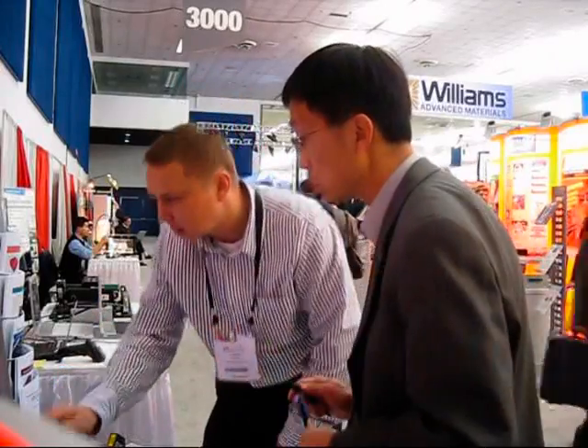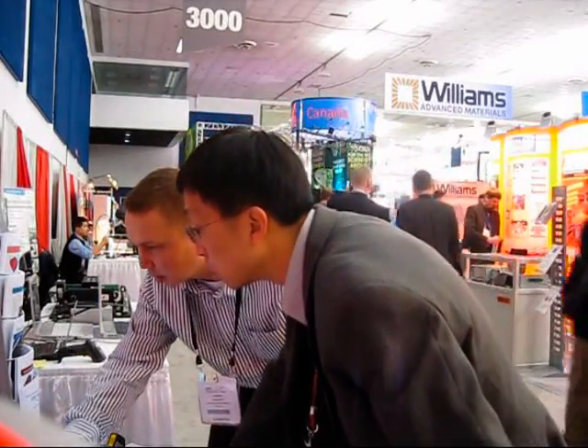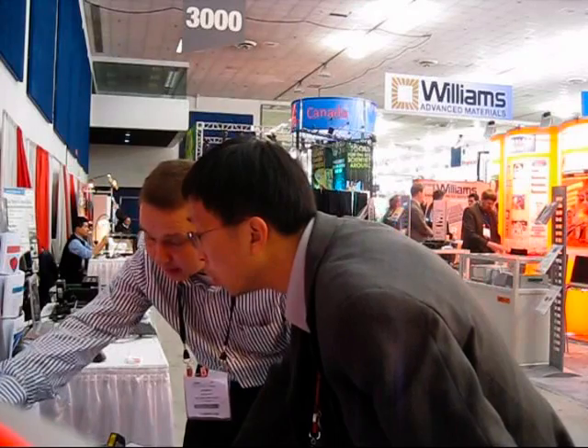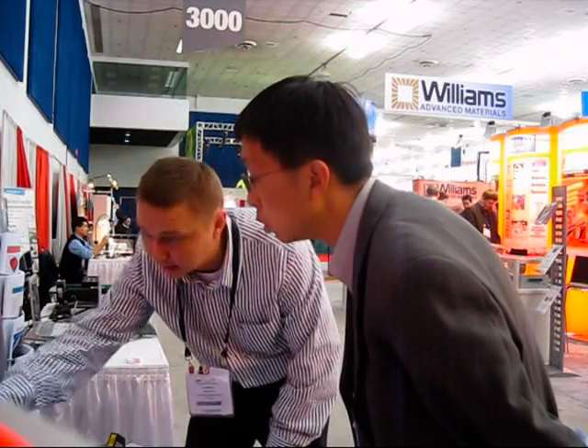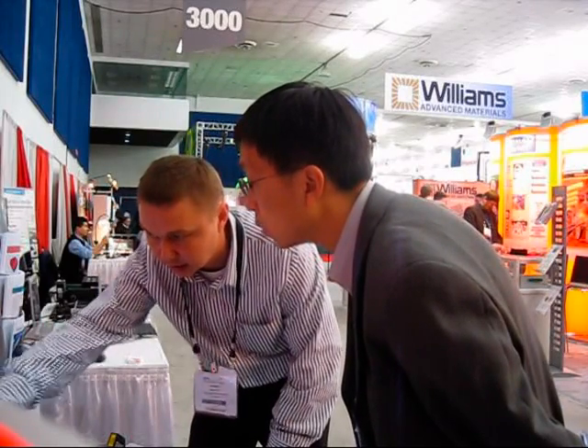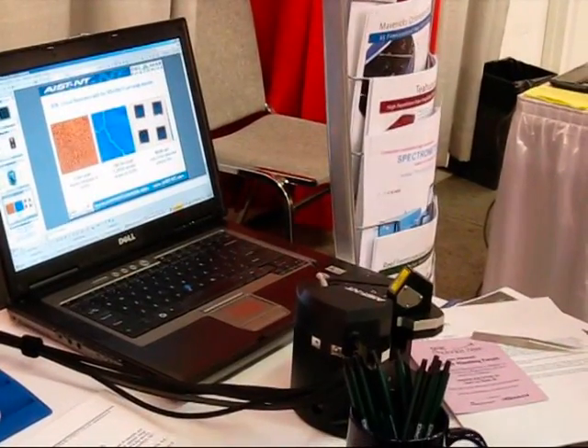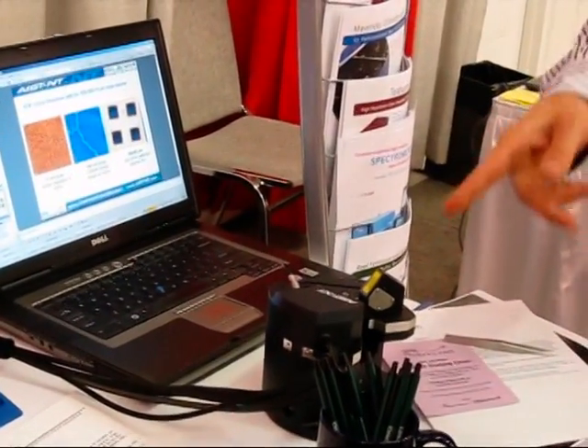Can you show me this? The best resolution for nanoparticles — for this instrument — this is atomic resolution, and there was no filtering in Fourier space. And the same scanner — so you don't have to change scanners to get this or this. This is 90 by 90 microns, this is 10 Hz, 15 Hz. Actually, this scanner was built to be fast.